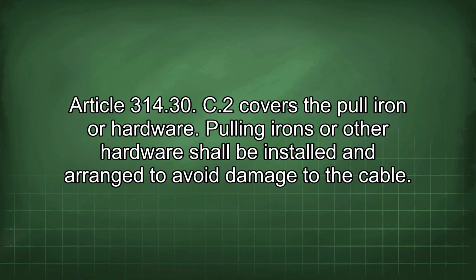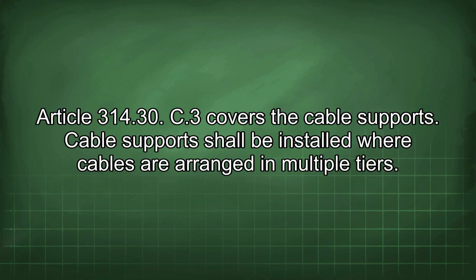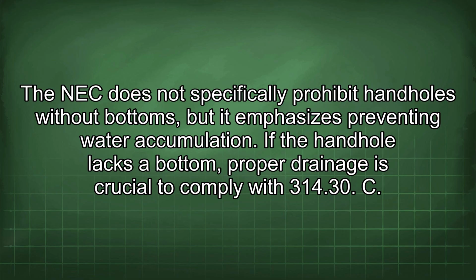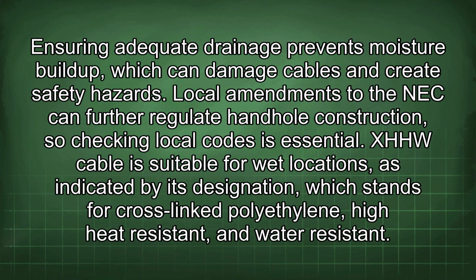Article 314.30(C)(2) covers the pulling irons or hardware. Pulling irons or other hardware shall be installed and arranged to avoid damage to the cable. Article 314.30(C)(3) covers the cable supports. Cable supports shall be installed where cables are arranged in multiple tiers. The NEC does not specifically prohibit handholes without bottoms, but it emphasizes preventing water accumulation. If the handhole lacks a bottom, proper drainage is crucial to comply with 314.30(C). Ensuring adequate drainage prevents moisture buildup, which can damage cables and create safety hazards.